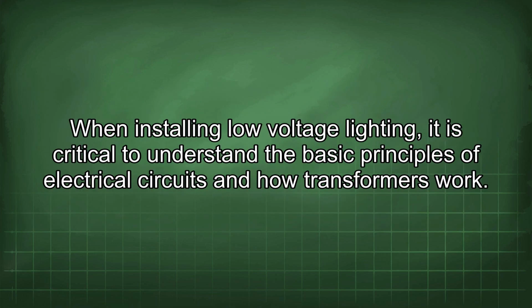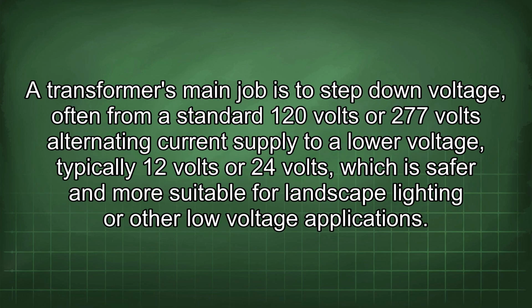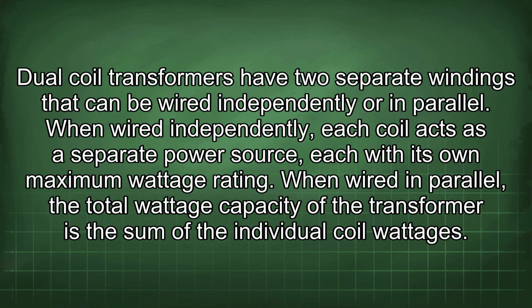When installing low-voltage lighting, it is critical to understand the basic principles of electrical circuits and how transformers work. A transformer's main job is to step down voltage, often from a standard 120 volts or 277 volts alternating current supply to a lower voltage, typically 12 volts or 24 volts, which is safer and more suitable for landscape lighting or other low-voltage applications. Dual-coil transformers have two separate windings that can be wired independently or in parallel.